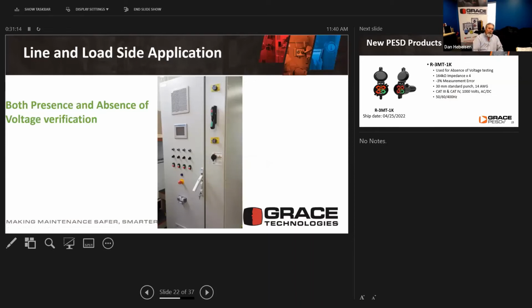Here's an example of a customer who took the opportunity to create a situation where they are using a visual indicator at the top above the disconnect. And that's really reminding people that the incoming energy is still there in the cabinet. And then you've got your disconnect. Below the disconnect, you've got another voltage indicator, again, voltage presence. And then beneath that, you have the safe test point. So now if you were going to lock out at this particular cabinet, you could come up to the equipment and see that the line side is flashing, the load side is also flashing.